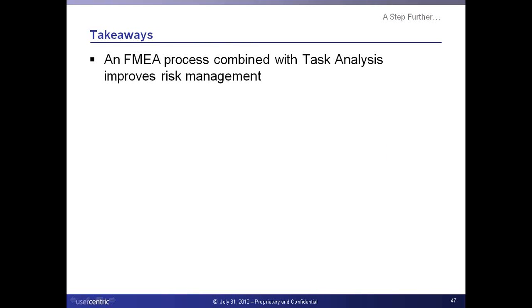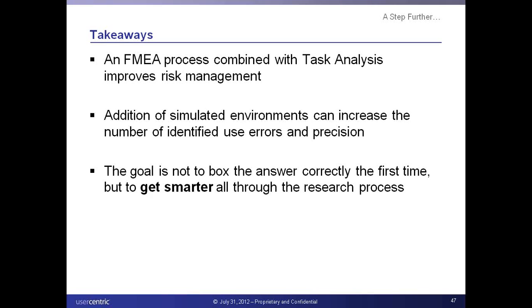What I want you to take away from this is the FMEA is really a risk management tool. It starts with the task analysis. By adding simulated environments, you can increase the number of use errors that you find, as well as precision. The goal here is not necessarily to create an FMEA the first time, but through the process towards a 510K application, you get smarter and you add to the FMEA. So this is in some ways a living document up until the 510K submission is provided.